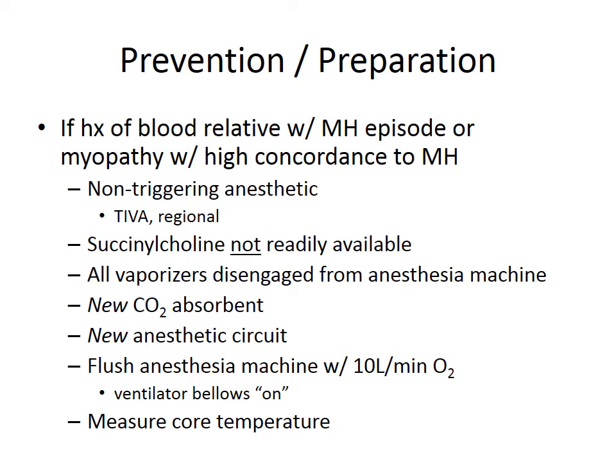Since we always have succinylcholine as a rescue drug that is readily available, it's important to make sure that succinylcholine is not readily available, since giving it in a case when you think perhaps it's needed in an emergency and not recognizing that this is an MH-susceptible patient, it could inadvertently cause this type of response. So all vaporizers should be disengaged from the anesthesia machine.